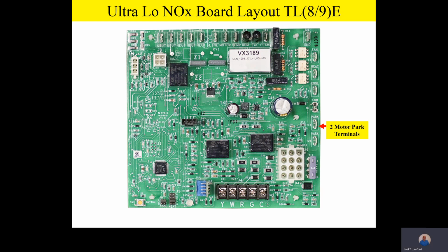Here we have two park terminals, two motor park terminals. These park terminals are designed for nothing more than to put unused motor taps or unused motor speed wires on the board. So instead of just taping them off, we give you a nice convenient place to put them on these park terminals. It should be noted the park terminals are just blank terminals, a convenient place to put the unused motor speed taps.